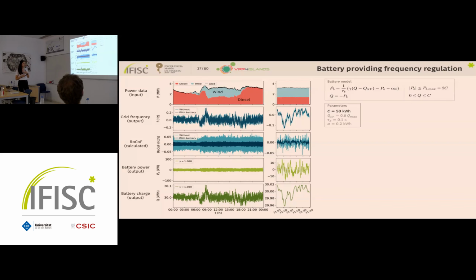Starting with gamma equal to 1, we have here the power mix: the input data for the model, the grid frequency given by the model, the rate of change of frequency (ROCOF) calculated from the frequency, and also the battery power and charge. We can see that including this small battery with gamma equal to 1 reduces the frequency fluctuations, but not very much. However, the ROCOF is quite reduced, and this comes at the cost of having very small deviations of the power as well as the charge.